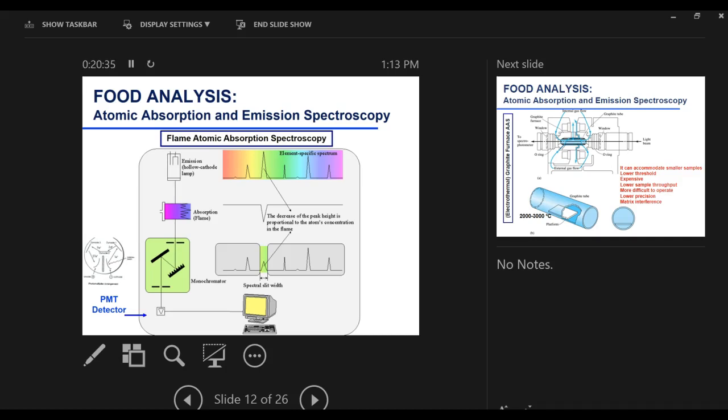Okay. So today we were talking about slit width. And like for calcium, I believe the slit width is set at 0.7. That would be 0.7 nanometers, correct? Yes, it's in nanometers. And then for iron, it's like point something. I think it's much less. Much less. Is that because of the peak? I'm looking at this liquid spectrum. Can you remember what the wavelength in nanometers was for iron? 248. 248. Okay. And 422 for calcium.